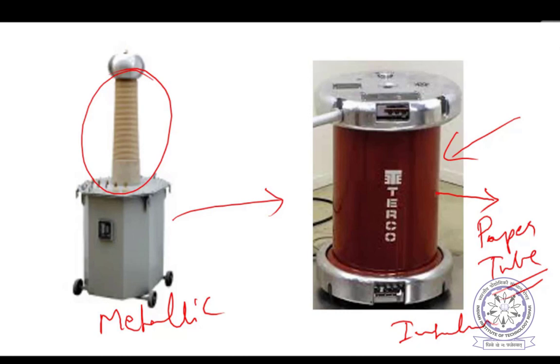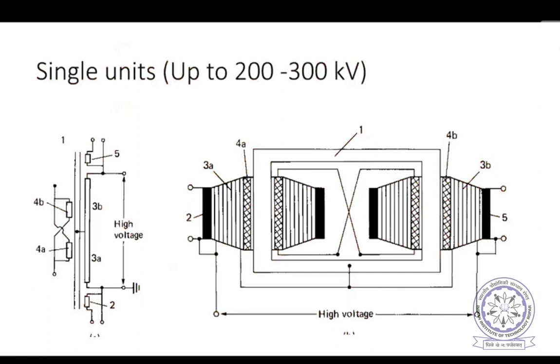Now for single units up to higher voltages, there is a small constructional change. The winding is split into two parts, and instead of grounding the core, the core will be at the midpoint potential. The midpoint of the winding is connected to the core like this. You can see, 50% is here, 50% is above.